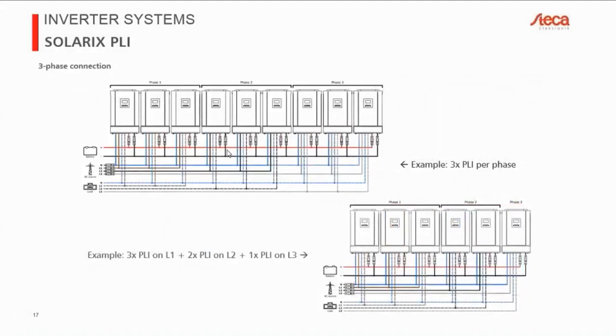And then if you want to go even bigger, as I said, the maximum is 9 inverters in a single synchronized system. So that would be this in a 3-phase system. But you can also use asymmetrical phases. You can go ahead and put, in this case, 3 inverters on phase 1, 2 inverters on phase 2, and 1 on phase 3. You can even go ahead and use 7 inverters on phase 1 and 1 each on phase 2 and 3. So you're very flexible in how you distribute those inverters. So for example, if you have a house, most of the house is running on a single phase, so you want to put 2 or 3 or more inverters on one phase, and then maybe you have just a few 3-phase loads, and in that case, you would maybe need just 1 inverter for each of the other phases.